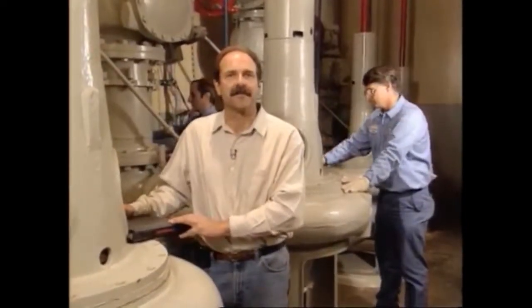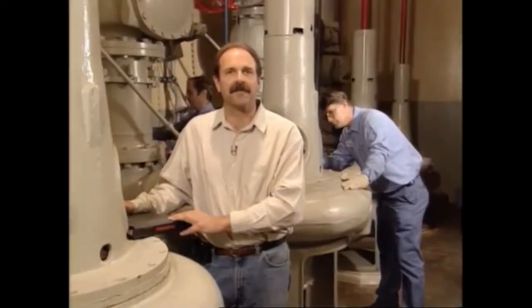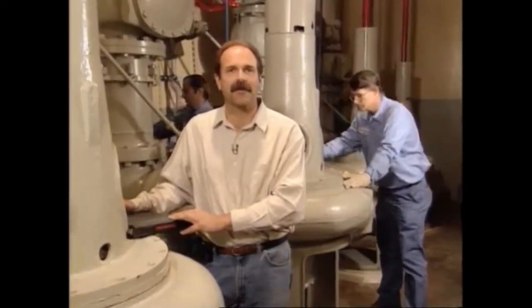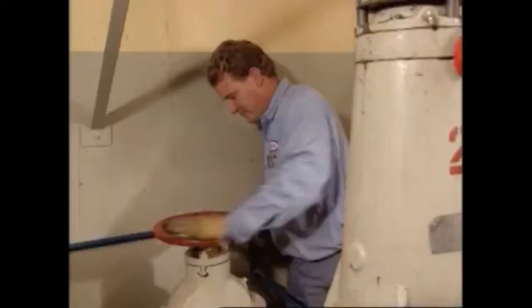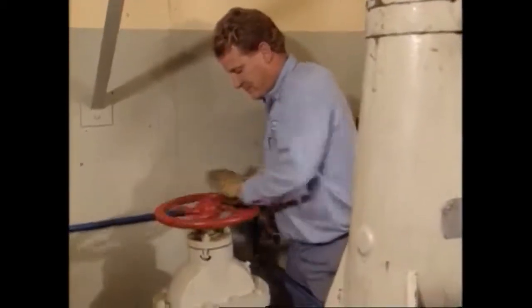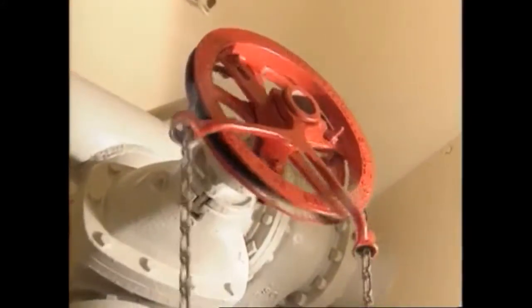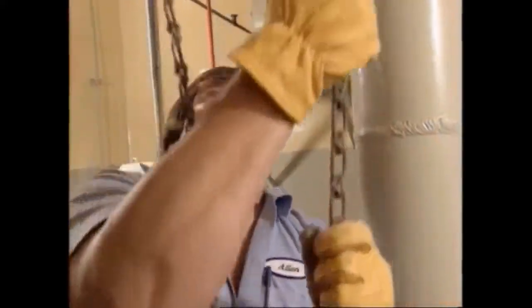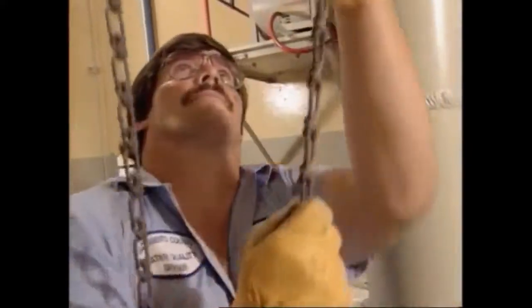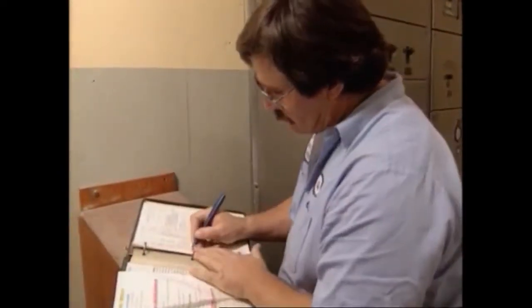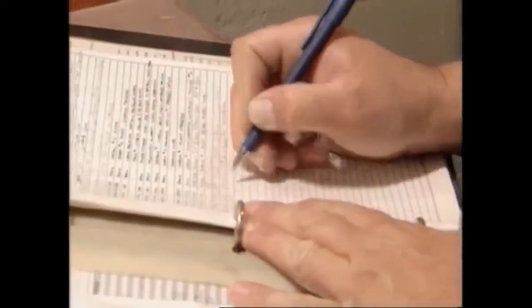Occasionally, supervisors must inspect the station after a crew visit to make sure that the tasks were performed and not merely signed off. Once procedures and objectives have established that specified tasks must be done on a routine frequency, whether daily, weekly, monthly, quarterly, or annually, the operators responsible for the lift station must accept the responsibility and be sure the tasks are completed when scheduled, so the operation of a lift station will be as reliable as possible. It's your responsibility as a professional. Analysis of the records can indicate if adjustments in the frequency of the tasks are necessary.